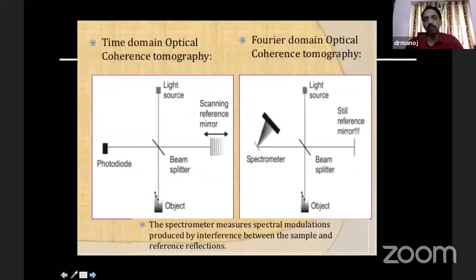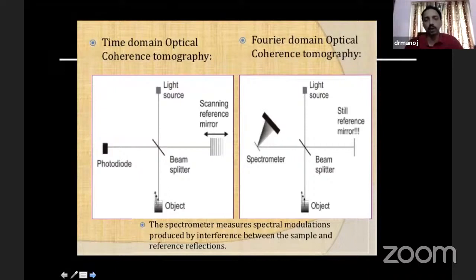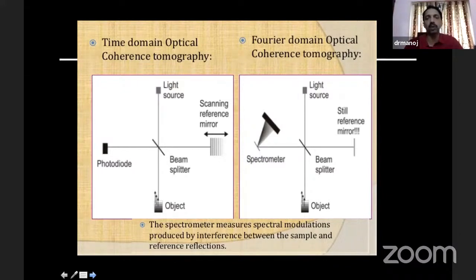From the light source, the light from these machines is split into two beams. One beam goes to the eye and the other beam goes to a scanning or reference mirror. The reflected light from the reference mirror and from the eye is integrated, and the interference between these two waves is interpreted — that is how we understand the reflectivity of the tissue we are studying. This is basically the principle of interference.